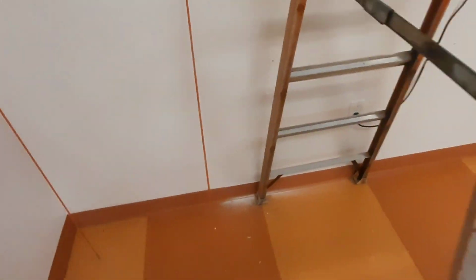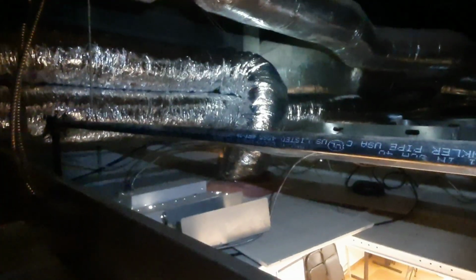Now we got our wire. I am probably gonna leave the excess wire up here. I'll secure it somehow, at least get a wire tie on it, but I don't know why this box was just not used, never wired or anything. So worst case scenario, they come back to me 5 years from now and say, hey, we want to connect that again, or we want to add another box and connect that side again. I'm just going to leave myself some leeway with that wire. I did the same thing with the flex, just in case they said, oh, well, dude, that supply is blowing on me, can we move it or whatever. I left myself a little bit of play there, just in case, because you never know. So let's get this stat wired in and we'll plug into the box and see what we got.